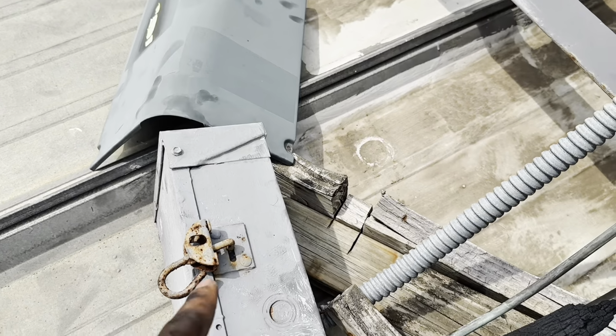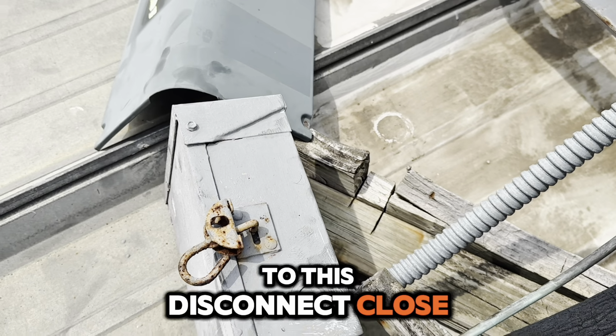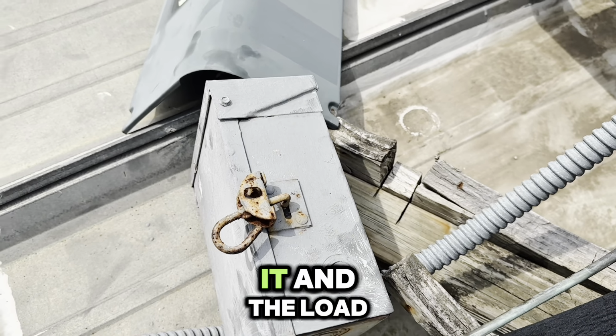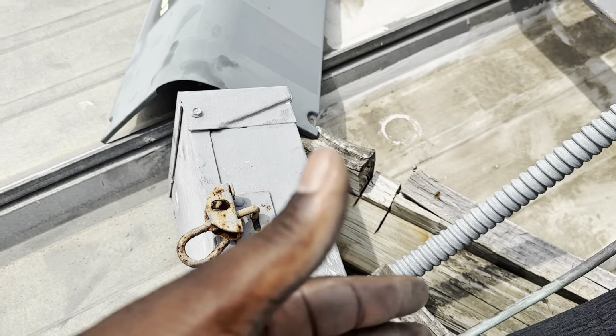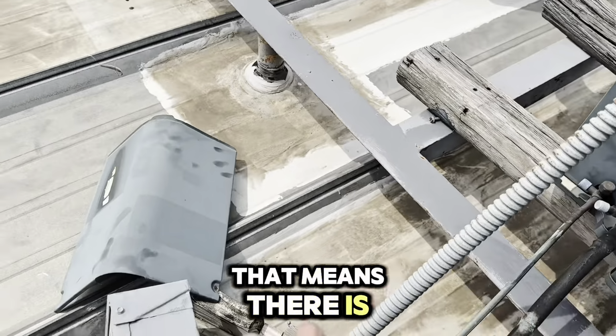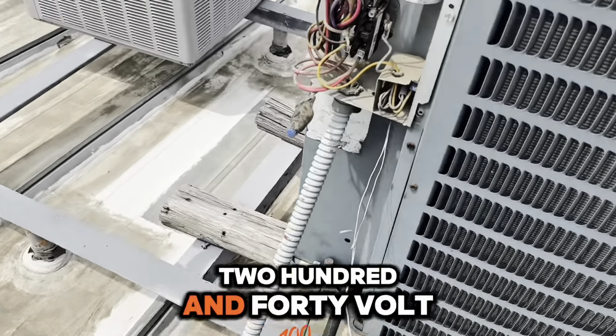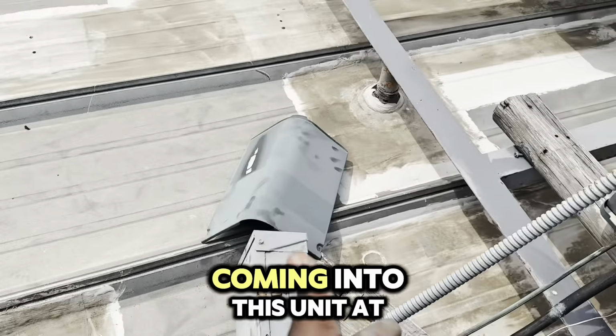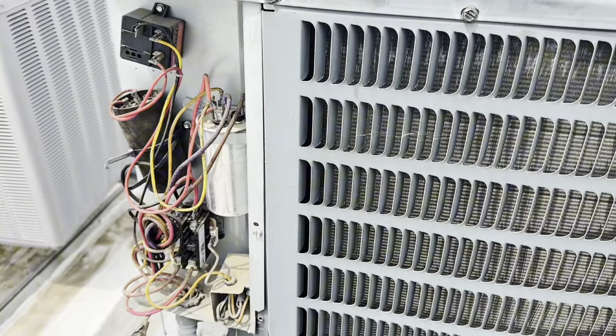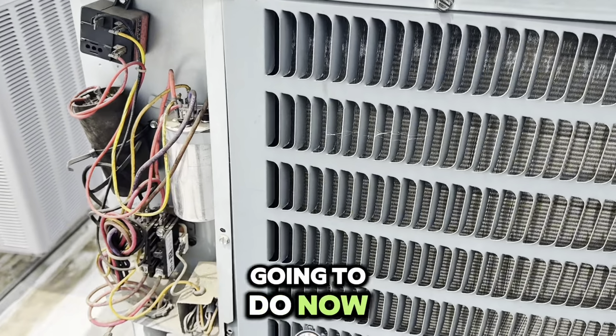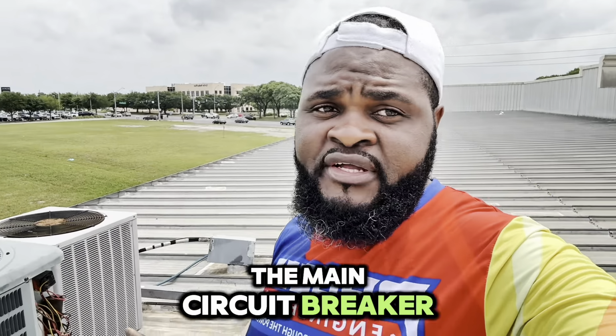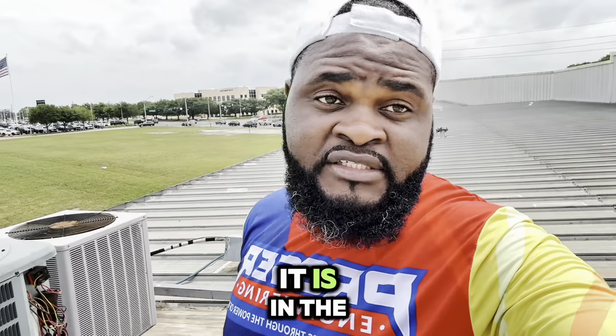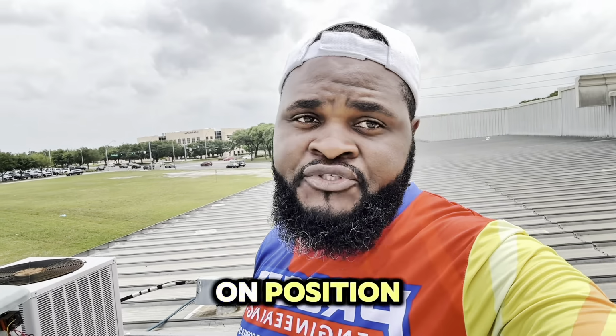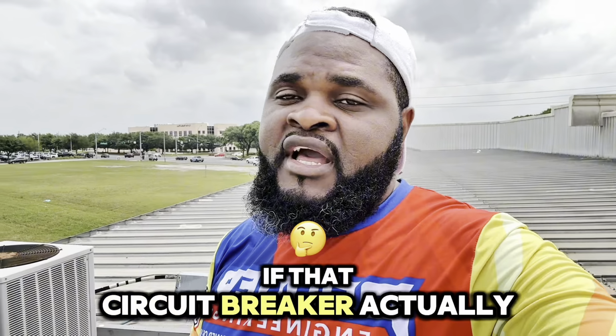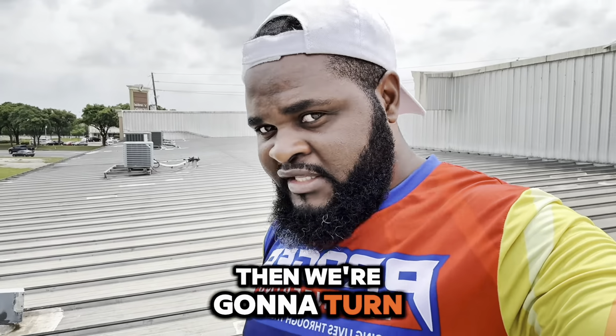We came back to this disconnect close to the unit. We open it and the load doesn't have any power. That means there is no 240 volt coming into this unit at this point. So what we are going to do now, we're going to look for the main circuit breaker and make sure that it is in the on position. If that circuit breaker actually trips off, then we're gonna turn it on.